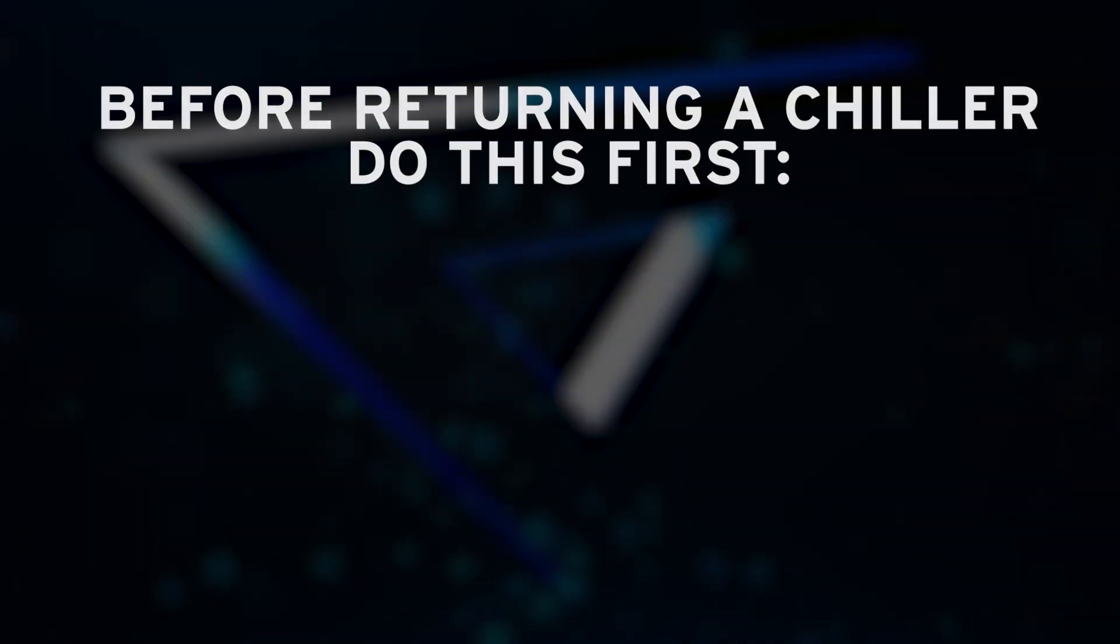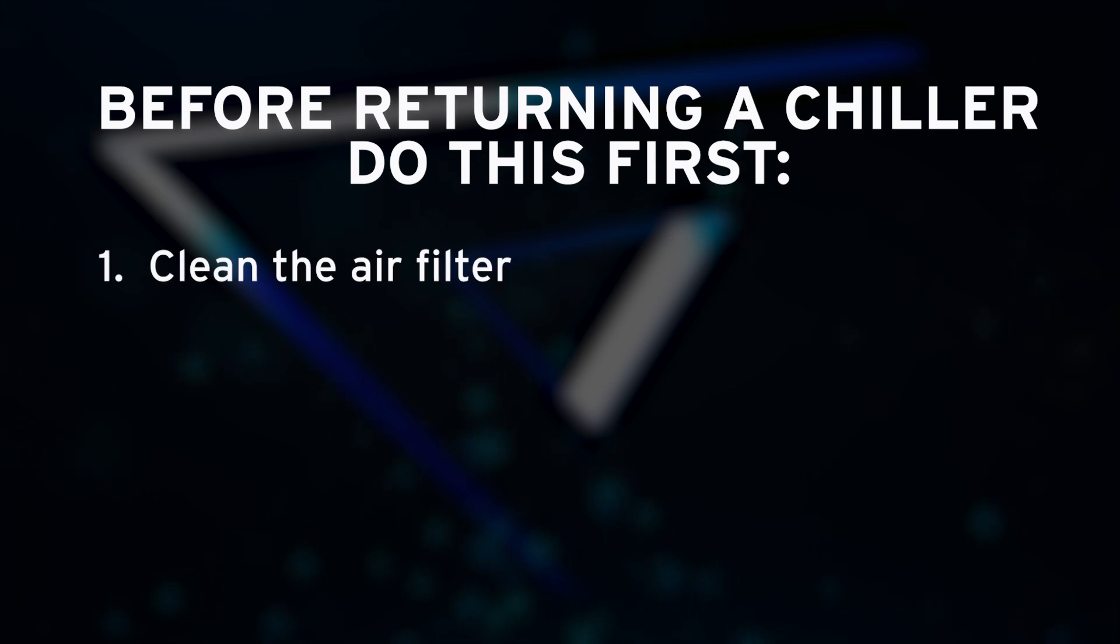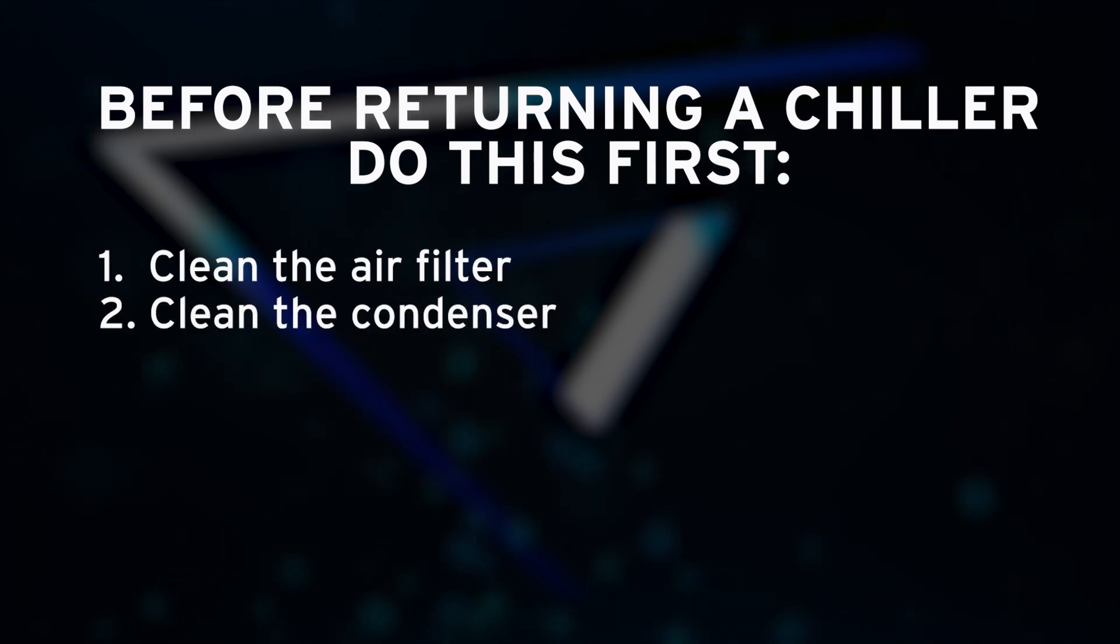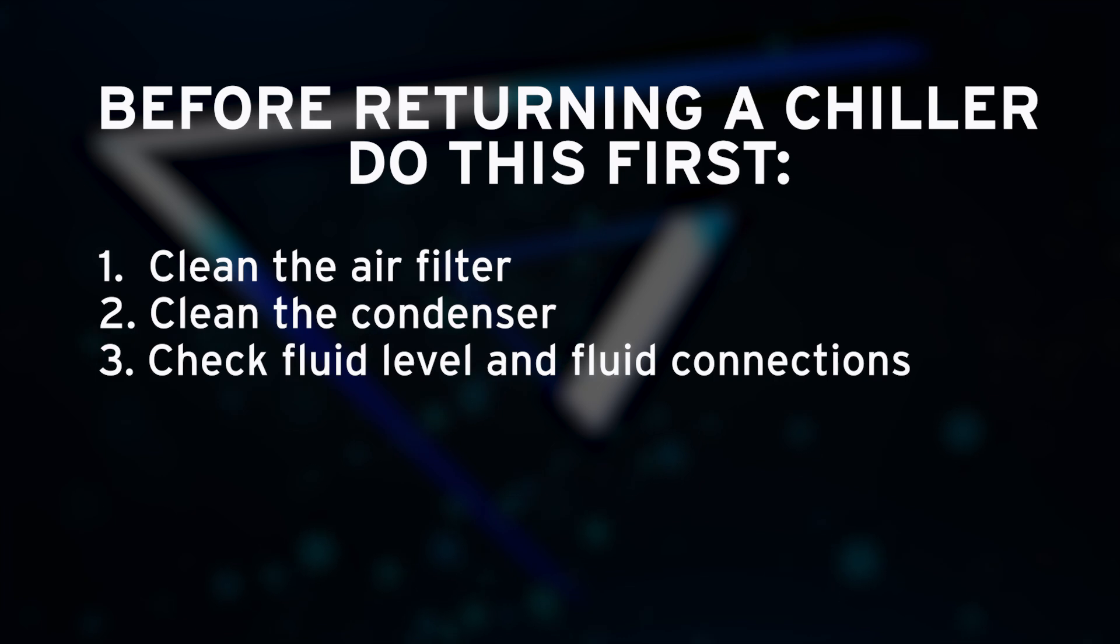Troubleshooting. Before returning a chiller, do this first. Clean the air filter. Clean the condenser. Check fluid level and fluid connections.